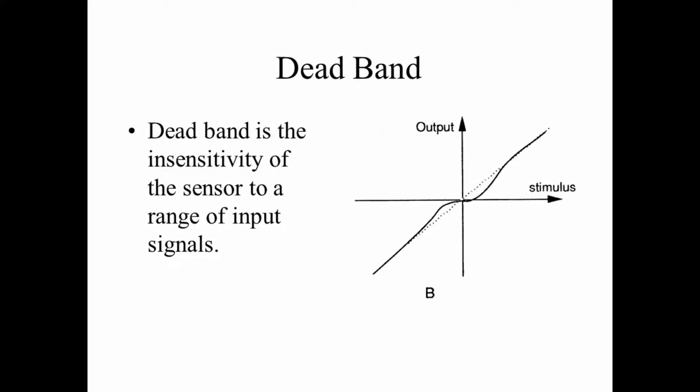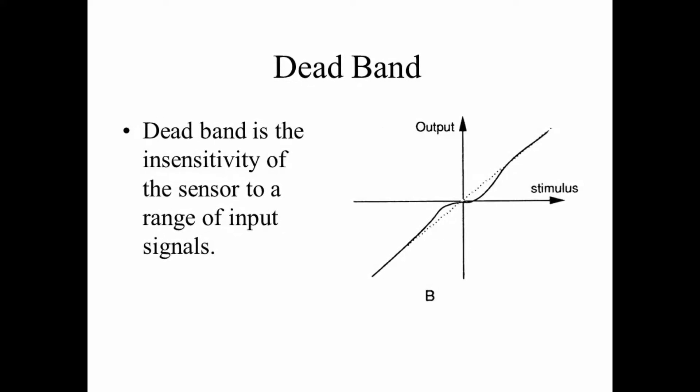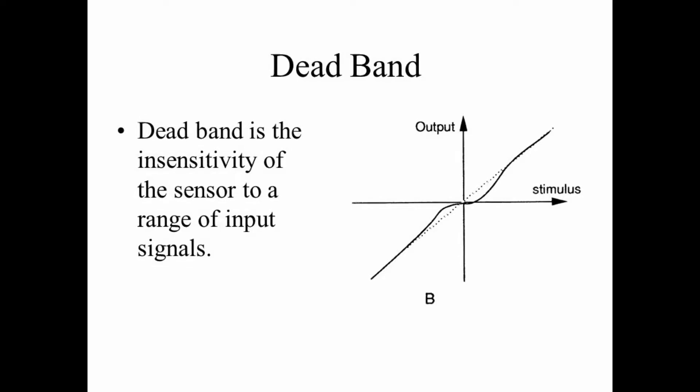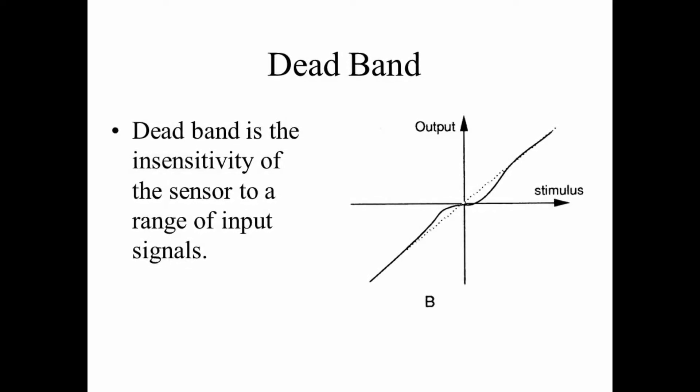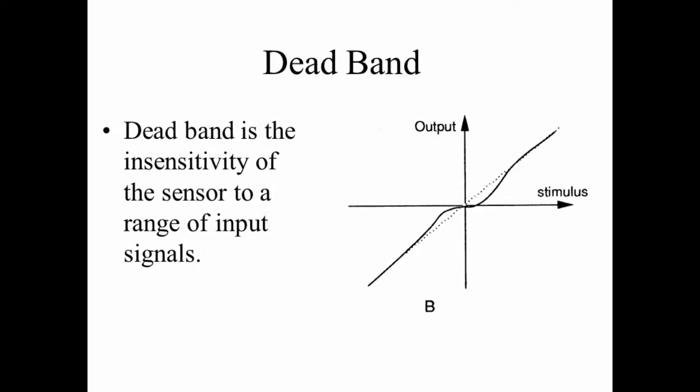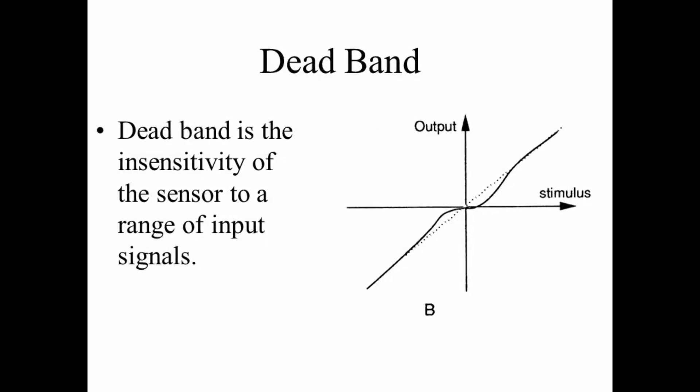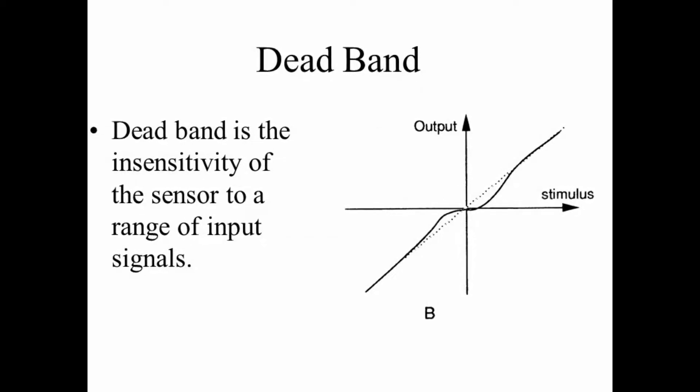Dead band is a region of pressure where change in pressure produces no change in measurement output or control signal. Many types of pressure sensing devices have a region slightly above and below zero pressure where the output does not vary.